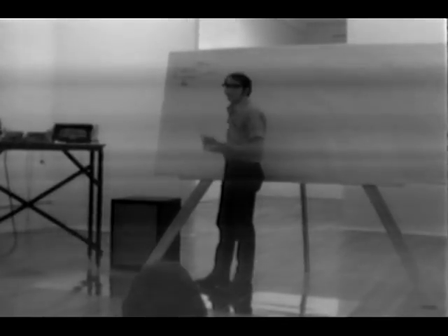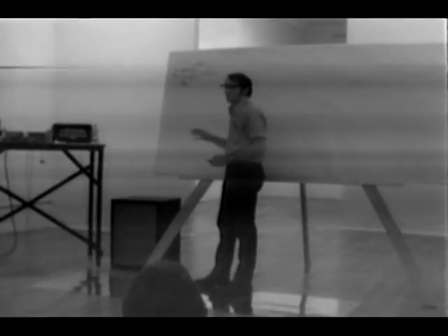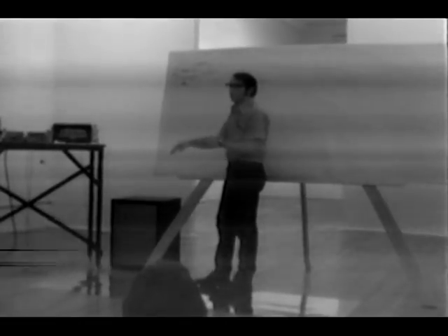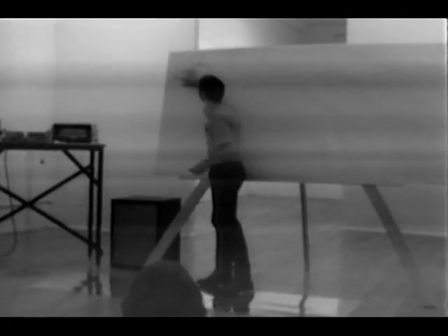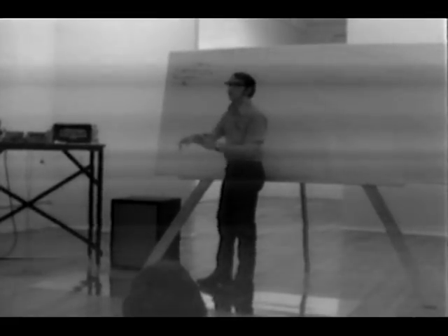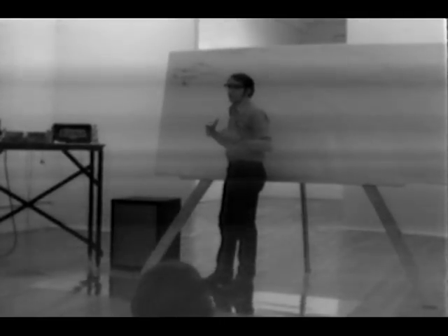Unfortunately, you're probably all aware when you unplug a plug from a hi-fi or something, you get a buzz. And what that is, is 60 cycle from the AC lines that are all over. You can't get away from this stuff. And so it'll completely mask the signal that you're trying to measure on your skin. So you use this differential amplifier configuration, and your whole body is picking up the 60 cycle frequency like an antenna.